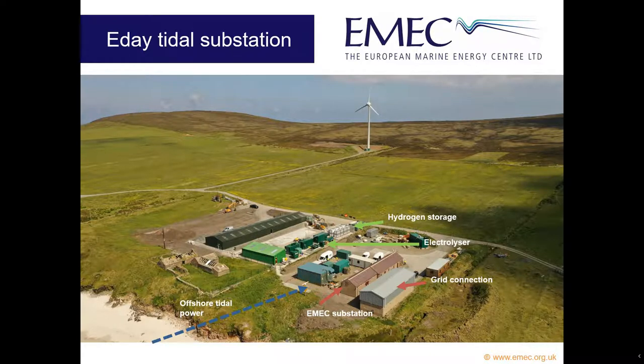So the storage issue has changed, our focus has changed. We've now recently completed a flow cell battery storage site, which has got a 1.8 megawatt hour, 600 kilowatt flow cell battery system in there, made up of around 35 kilowatt units, which we charge from the tides and also from the local wind turbine.